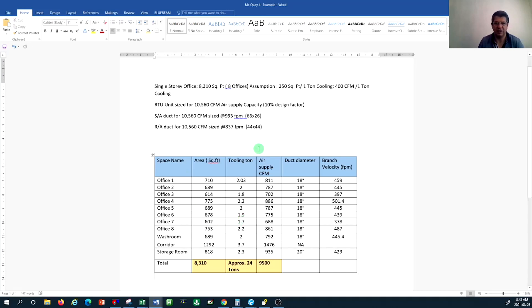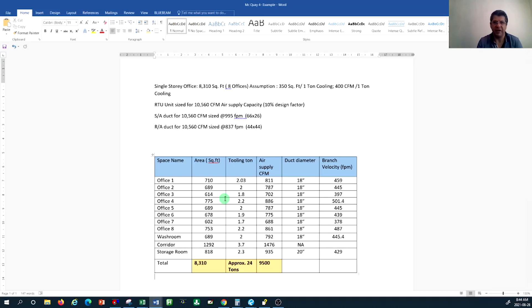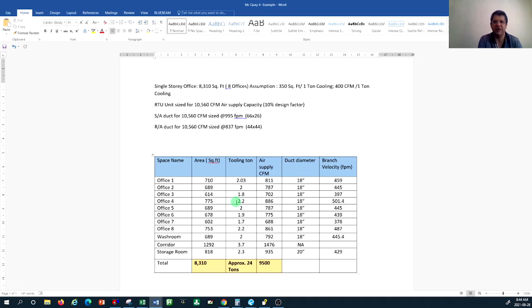For the sake of these examples I did the rule of thumb calculation, and based on the cooling required, we estimated the air supply required based on 400 CFM per ton of cooling. Then based on that we started sizing our duct work. Remember there are a variety of parameters to consider even if you do equal friction duct sizing — you want to check your velocity and make sure it complies with the required noise criteria in different spaces.